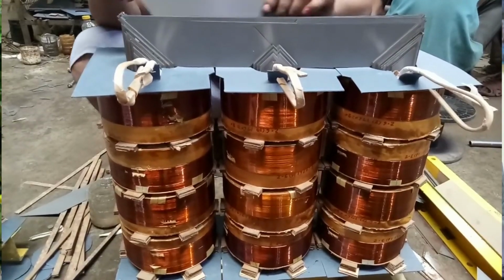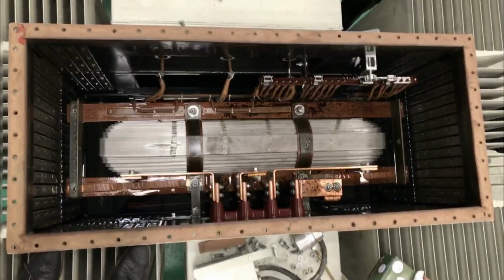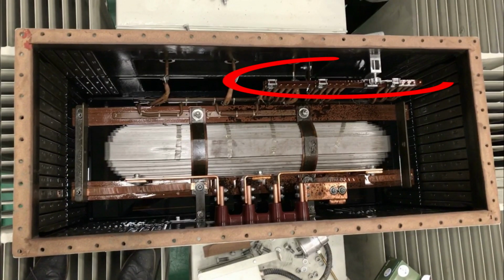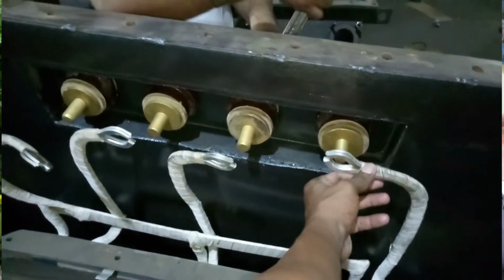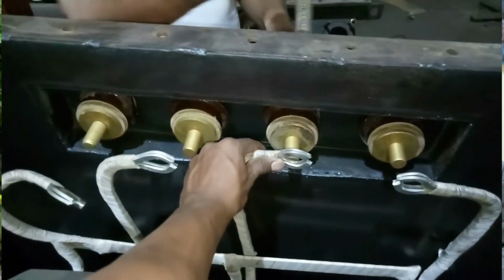So back to the transformer. The transformer has the conductive parts, the windings, which are themselves insulated and separated from each other and immersed in the oil, which is also an insulator. The high voltage windings are connected to the tap changer, which has taps, and then the terminals are brought outside the transformer tank and supported by bushings, which are themselves insulators.